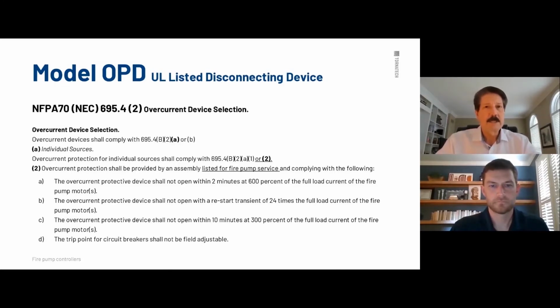The key for the OPD, as compared to a safety switch, fusible switches are acceptable, and that's fine, but you need to make sure, number one, that you're sizing the fuses properly. Number two, that you're using the correct size fuse for interrupting capacity. And typically, when you get into that size, 6 times full load amperage, your fusible switch is quite large, and you know how pump rooms are. They're not very big. This is going to take a large section of space on the wall, or however you're going to mount this, where an OPD is going to be maybe a third or less. And that's really critical when you talk about space. And it's a circuit breaker, so it can be reset.